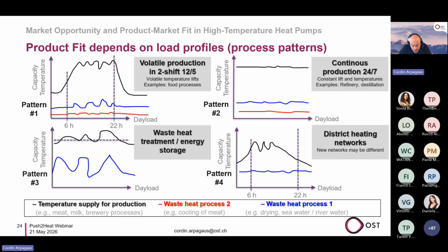And another important point is then the load profile. So what is the capacity or the temperature need over the day at the company? And here we have some handwritten drawings, but we can imagine a company with a very volatile production, a two-shift operation, start at 6 o'clock in the morning, and then we have the production. And here on the other side, we have a more continuous process, a company that has always need of process heat. And we also see the waste heat sources that are needed to be accessed with the heat pump.